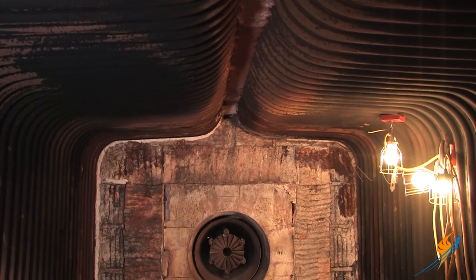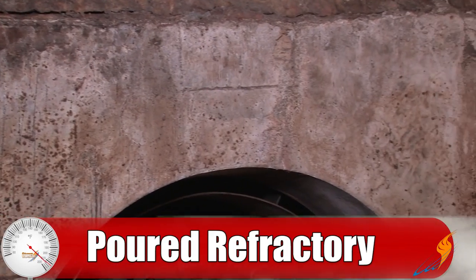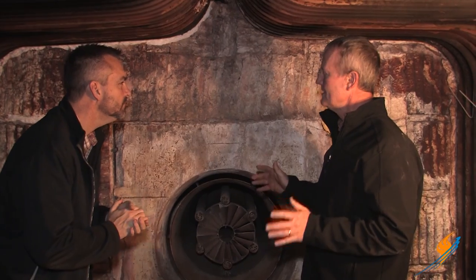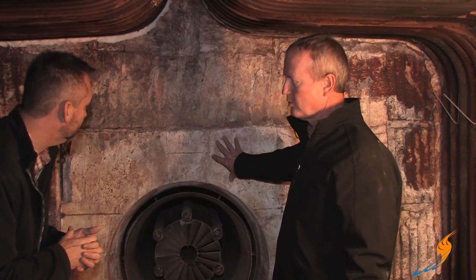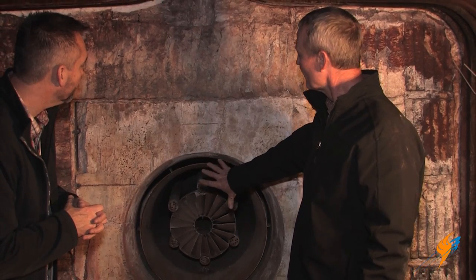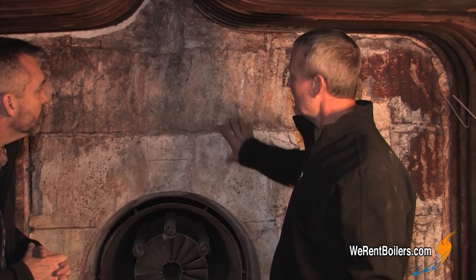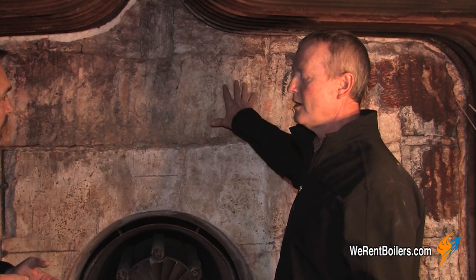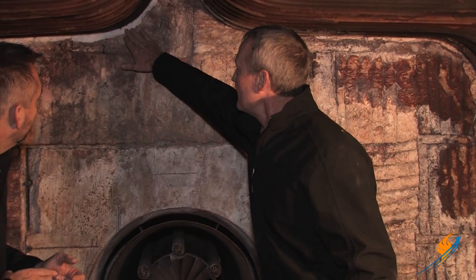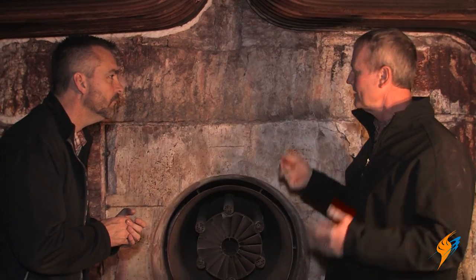Let's move on to the front wall of the boiler. The first thing I notice here, Stephen, is that I have a poured refractory which is hard, and a little bit softer more blanket-type. Pretty much everybody in the rental industry does this for two reasons. This reflects heat, or this will absorb heat. You have to have a hard refractory to finish the throat forming for the burner, to get the flame shape and everything right, but that's all the hard refractory we need. Then we need something to lighten the load and not absorb heat to make the boiler system more efficient. So we use a light module-type refractory — it weighs hardly anything, holds up real well, reflects heat, doesn't absorb it. It just does a better job, and these things are bouncing up and down the road at 60–70 miles an hour, so it takes that vibration without any issues.